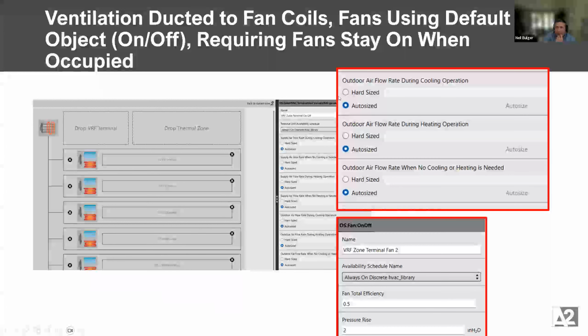So in the software, when we look in OpenStudio, there's this special little universe for VRF where you can make a system and then you make these fan coils. And what we've basically done is we've said for each fan coil, it has the option to bring in outside air in every mode, cooling, heating, or when there is no cooling and heating. And so we've left that and said, let's autosize, tell me what I need to do. And that will look at the room and say, it's an office, it needs this much fresh air. So that enables that direct air to come into the zone. If we don't have that, we'll see this in one of the DOAS cases, we would set these all to zero. And that would tell the unit, I'm only here for heating and cooling. I don't need to worry about conditioning a certain amount of ventilation air.